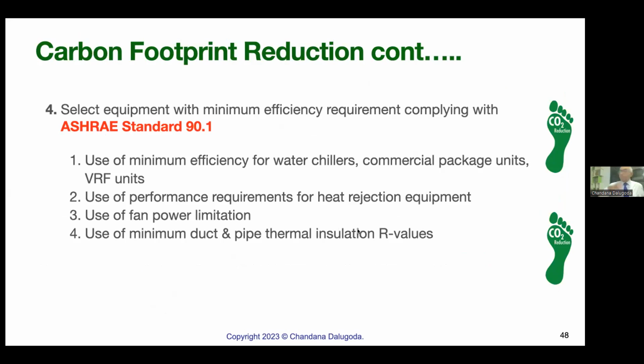That is, when we select a chiller, a commercial package unit, or a VRV unit, we'll have to comply with the energy efficiency limit. Either it is given in EER or COP or kilowatt per ton. Use performance requirements for heat rejecting equipment like cooling towers. There are performance standards for cooling towers. You just can't buy because it is cheap. No.